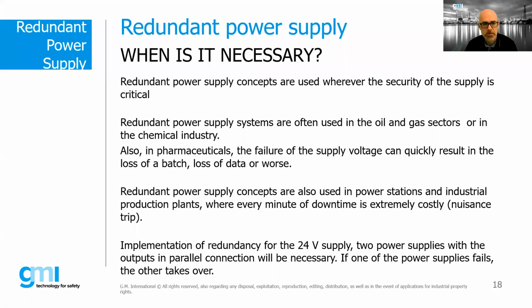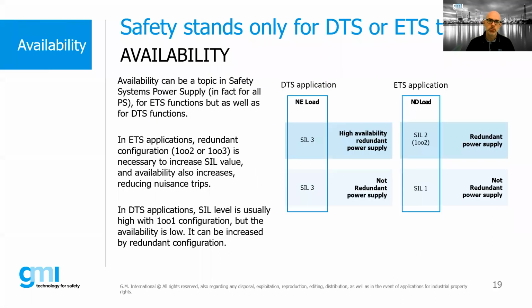Well, in the next slide, let's talk about system availability to the process. As we see from the slide on the screen, for de-energized to safe applications, typically normally energized loads, the SIL3 safety level is easily reached through a type 1 out of 1 configuration. For this type of application, we can achieve, through redundancy, an increase in availability to the process. This allows us a further quality step in guaranteeing production continuity at the plant and a higher safety level.